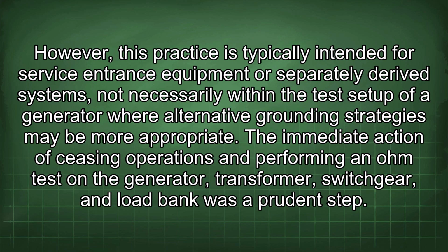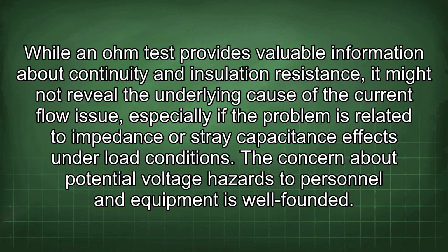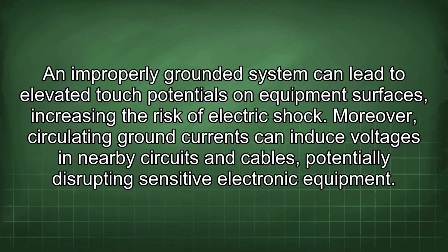The immediate action of ceasing operations and performing an ohm test on the generator, transformer, switchgear, and load bank was a prudent step. While an ohm test provides valuable information about continuity and insulation resistance, it might not reveal the underlying cause of the current flow issue, especially if the problem is related to impedance or stray capacitance effects under load conditions. The concern about potential voltage hazards to personnel and equipment is well founded. An improperly grounded system can lead to elevated touch potentials on equipment surfaces, increasing the risk of electric shock. Moreover, circulating ground currents can induce voltages in nearby circuits and cables, potentially disrupting sensitive electronic equipment.